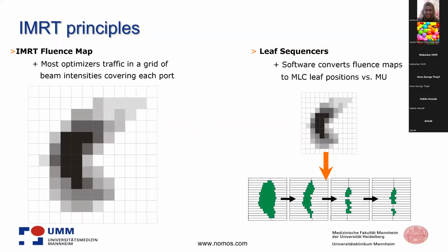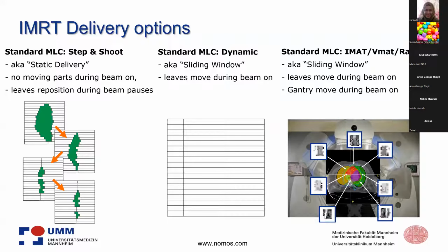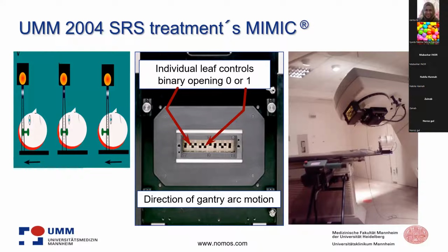So the delivery options are, as I said, at the beginning, the step and shoot approach. That means this was a static delivery, and no moving parts during beam on, leaf positions during beam pauses. The standard MLC dynamic was a window technique. That means the leaves are moving during beam on, and the next step was the sliding window technique, and the gantry is moving during beam on. We used, but you know, these MLC types, especially this MLC from the Siemens Mevatron, the leaf width was 1 cm in the isocenter.